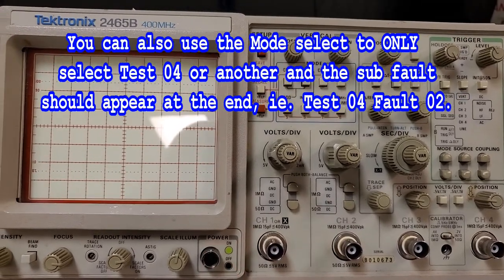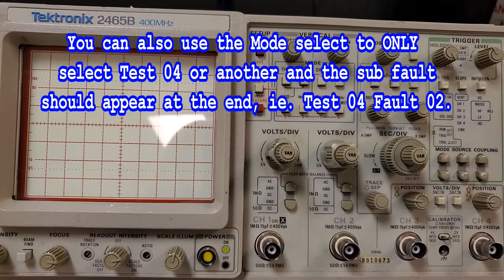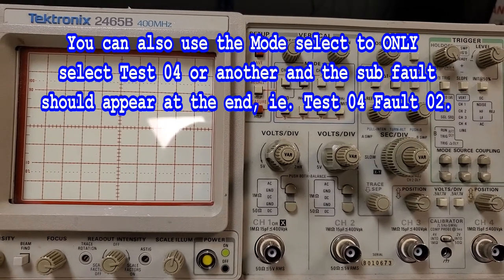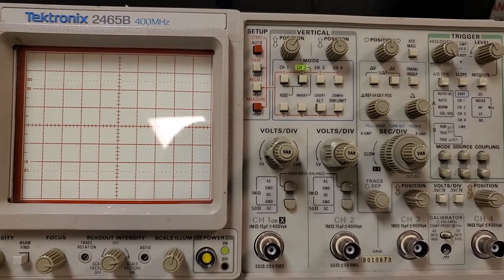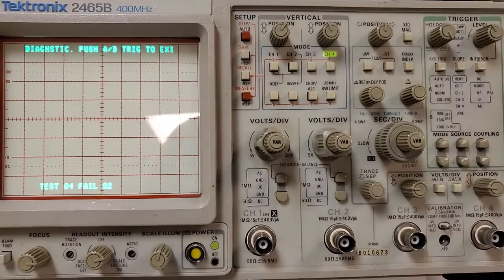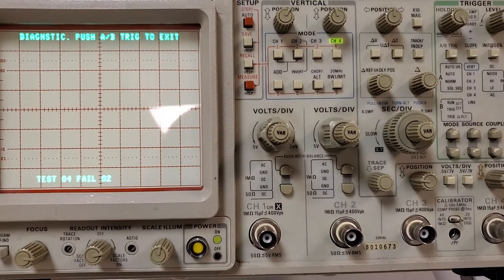So if it failed test four, there are a few tests that when you turn the scope off and turn it back on, it'll tell you - it'll automatically go into the diagnostic test to tell you there was a failure. It's powering up, see the lights are clicking, and mine failed test four number two. So let's go see what that is.